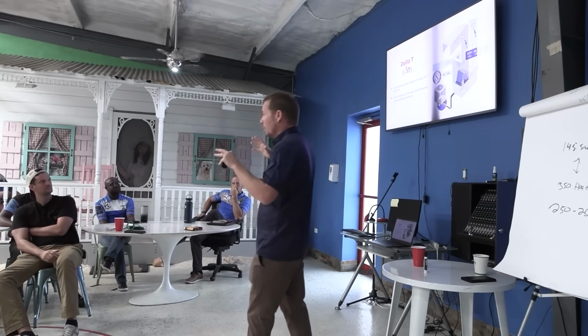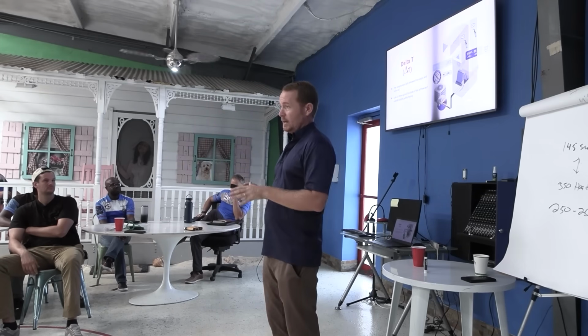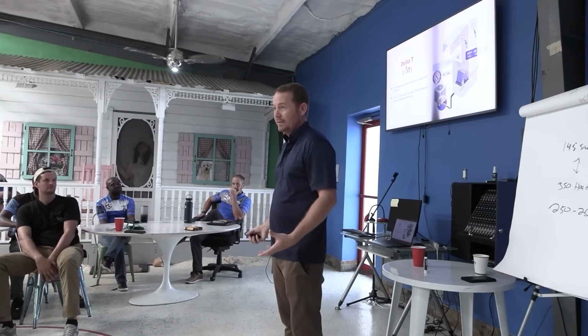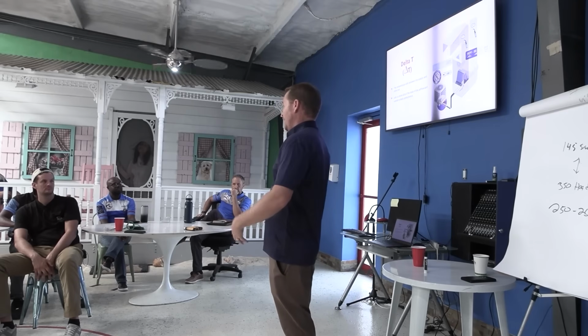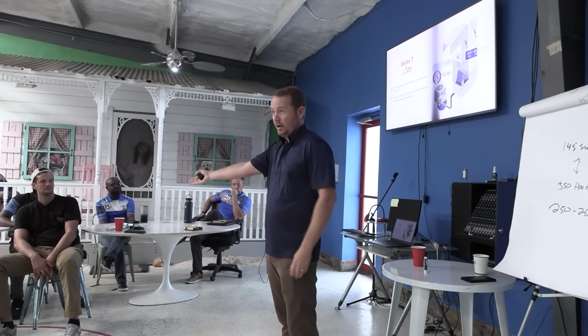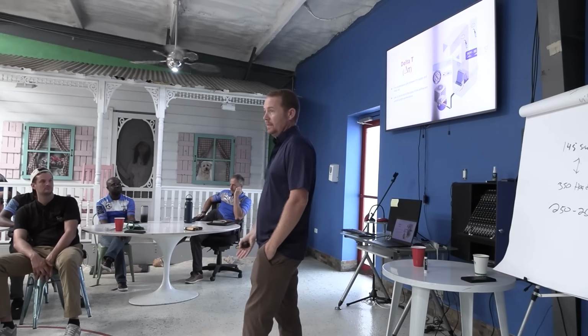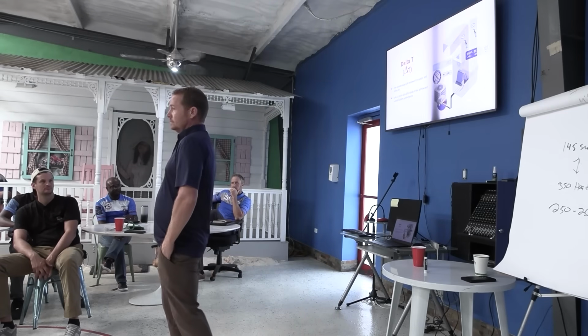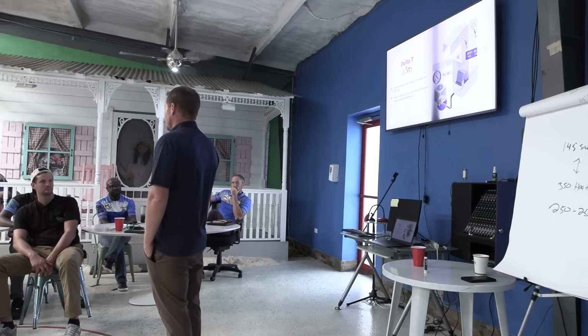Because the more humid the air is, and we're talking total humidity, when you start up a unit and it's really humid in there, and the drain is just raining on you, just pouring out water, your delta T is going to be low. You're going to see 14, 13 in some cases.